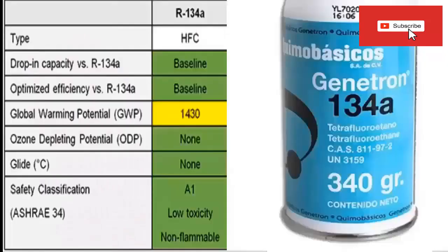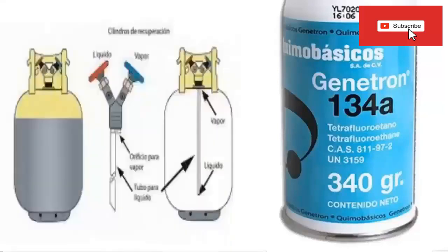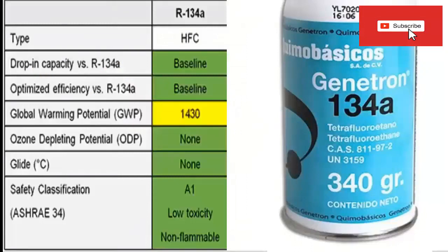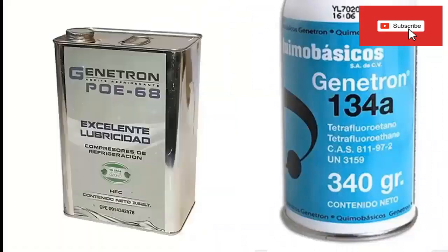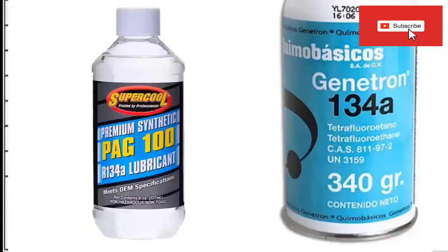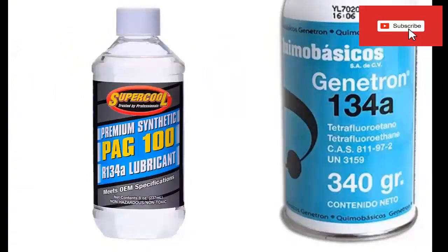11. Since R134a is a refrigerant with no mixed components, it can be charged in a liquid or gas state. 12. It is not necessary to turn the container with refrigerant or use the outlet of the liquid. 13. As the evaporator temperature value begins to drop, the charge by weight becomes more important. 14. R134a works with POE-type oil. 15. R134a is not miscible with mineral and alkylbenzene type oils. 16. R134a in automotive air conditioning applications uses PAG-type oil.